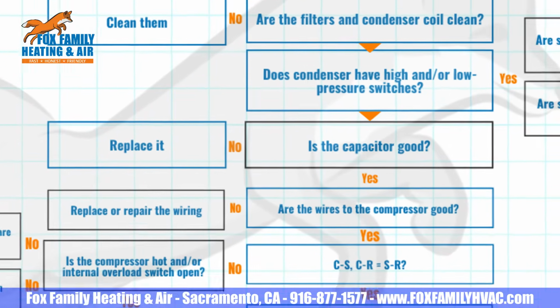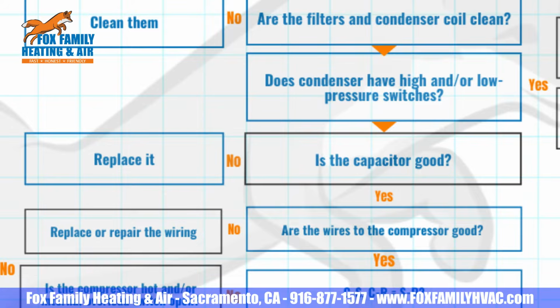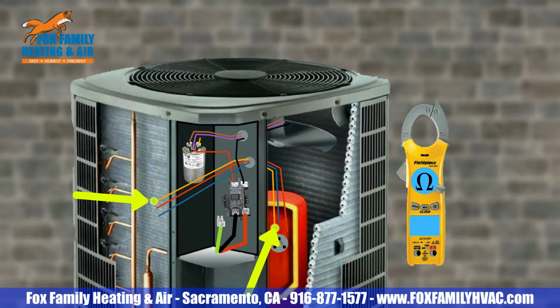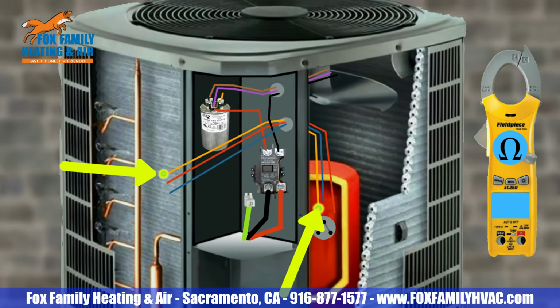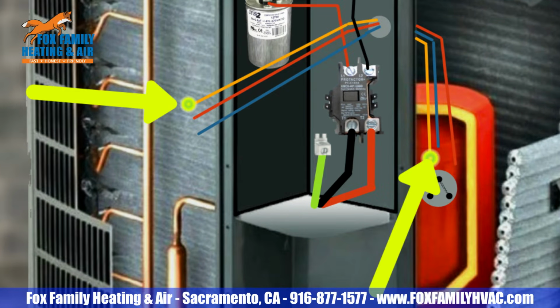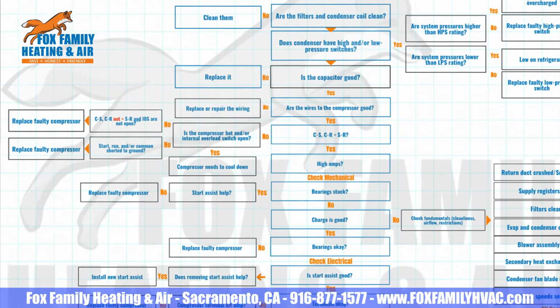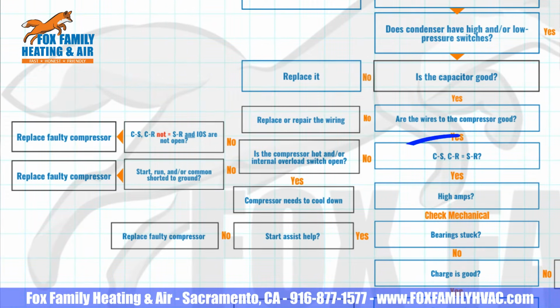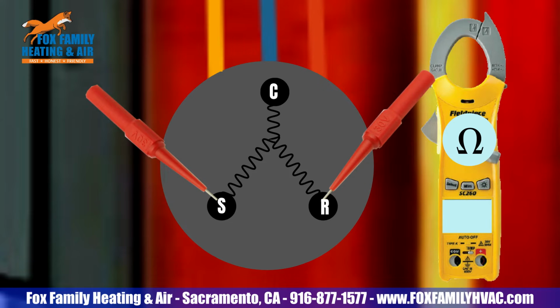Is the capacitor for the compressor good? If it's not, replace the capacitor. If the capacitor is charged properly, then we can move on to checking the wires leading to the compressor. Are they good? Check for continuity or high ohms resistance from one end of the wire to the other. And there's 3 of them going there. Also, check for any rubbing of the sheathing on the wires and replace any of the wires if the inner copper is exposed or if there's high ohms resistance. If the wires are good, let's continue by checking the windings of the compressor. But first, is the compressor hot to the touch? And please be careful checking. Keep that answer in mind as you check the ohms resistance at the compressor terminals.